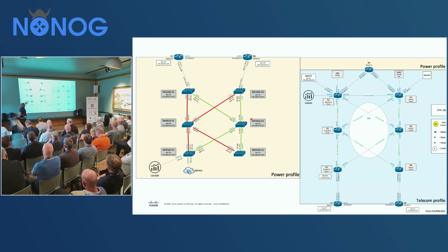And then if you look at the substation over here, as I said, in the network you are using the telecom profile, because that's the only way of transporting it over a longer distance. And in the substation, you are using the power profile. At the top of a substation, we have a device that can do interworking. So it will use the PTP telecom profile coming in, and through an interworking function, it will provide the power profile going into the substation. By doing so, we can utilize a common Grandmaster infrastructure, providing a proper power profile into the substation.